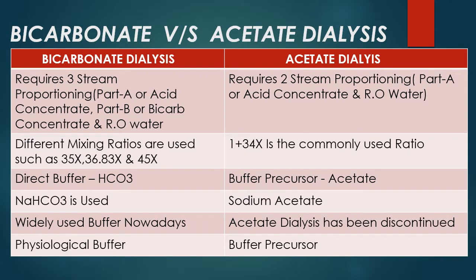If we compare bicarbonate and acetate dialysis: for bicarbonate dialysis, you will require a three-stream proportioning — that means Part A concentrate (acid concentrate), Part B concentrate (bicarb concentrate), and RO water. For acetate dialysis, you will require two-stream proportioning — that means a Part A containing acetate, along with RO water.